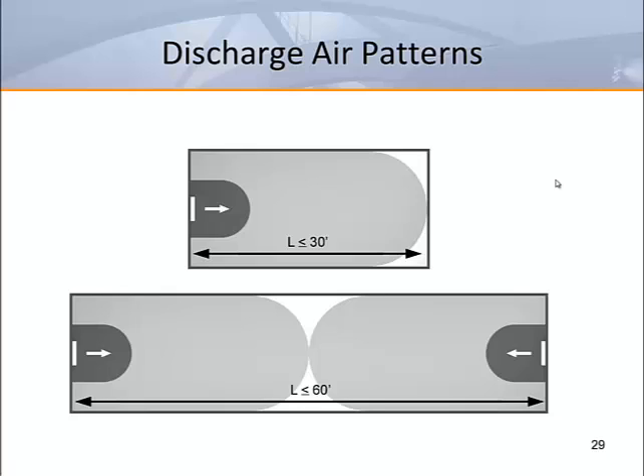With displacement ventilation, cool air is discharged into the space at less than 100 feet per minute, usually less than 80 feet per minute. Cool air falls to the floor and continues to travel across the floor until it reaches a heat source and stratifies. Air velocities above 50 feet per minute are usually considered to be the adjacent zone and clear of permanent occupants. The adjacent zone is identified by the dark area on the illustration shown. Typically, comfort conditioning is provided to the space until the velocity falls below 15 feet per minute. This usually means that the comfort area extends 5 to 6 times the distance of the adjacent zone.